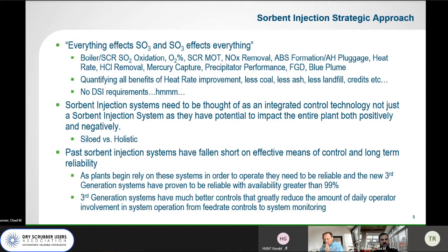So many people that have heard me talk have probably heard me say everything affects SO3 and SO3 affects everything. So basically that holds true from the coal pile to the stack. Your boiler and SCR basically oxidize your SO2 that comes from the coal, that creates the SO3. O2 percentage plays a role in that. SCR MOT is dependent on SO3. NOx removal can also be affected by your SO3. Air heater pluggage and ABS pluggage, it has SO3 as a role.